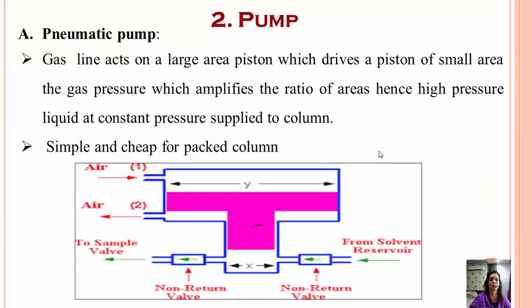The second component is the pump, where you pressurize the mobile phase. There are two different pumps. One is the pneumatic pump. The solvent comes from the mobile reservoir and there is a piston — with an air gap above and below it. When the mobile phase comes in, the piston drives over a small area and a large area; the ratio of these areas amplifies the pressure over the liquid, which then passes towards the column. That is the simple pneumatic pump, which is very cheap for high pressure chromatography.